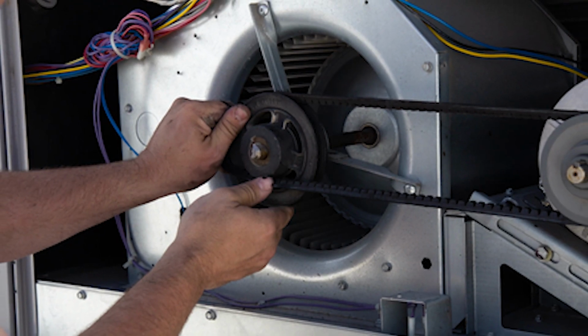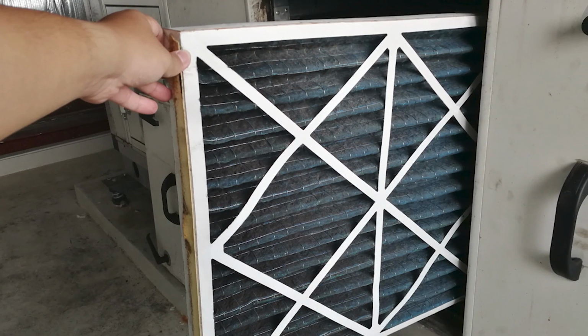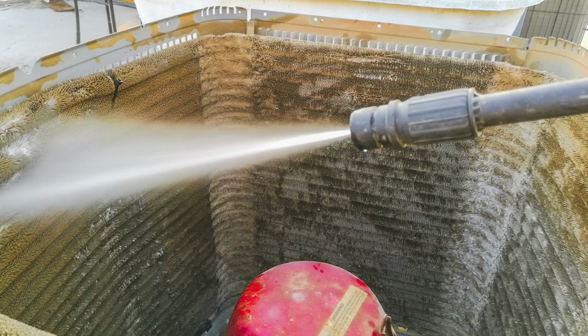The most expensive and time-consuming issue in any HVAC system that can arise due to neglected maintenance is compressor failure. Compressor failure is often linked to bad airflow, a result of bad belts, dirty filters, and plugged coils, all a result of neglected maintenance. Having low airflow across the evaporator coil can lead to frozen coils and eventually liquid floodback. If left unchecked, the compressor will burn out and must be replaced.